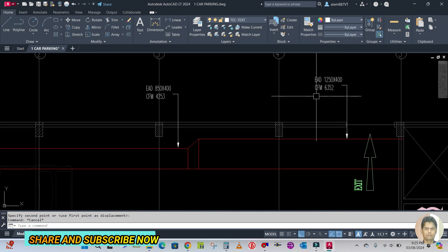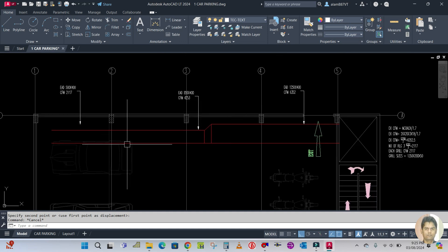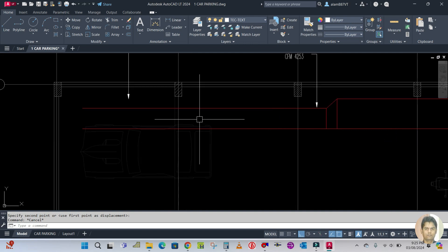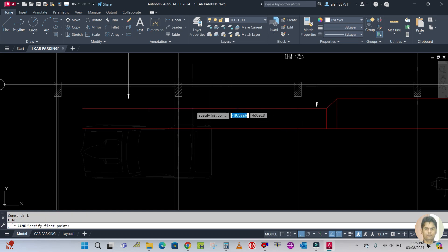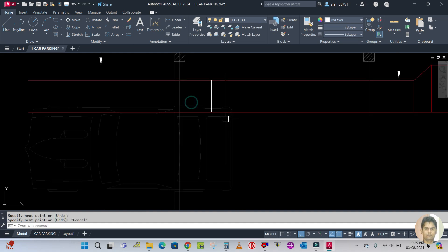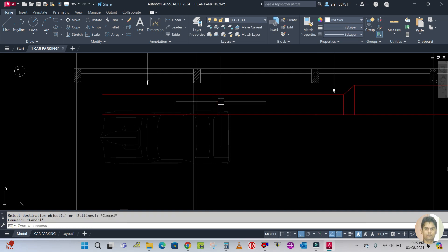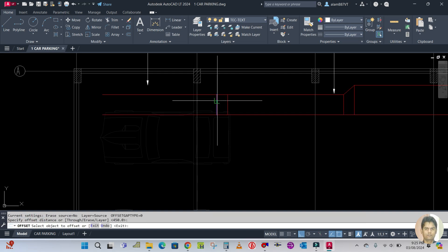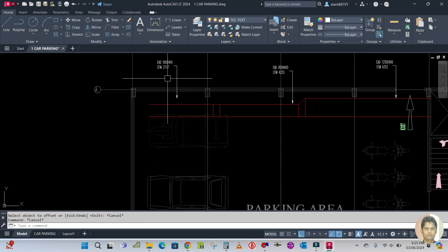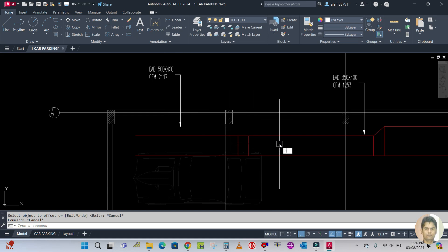The duct size here is 1250 by 400 and here is 850 by 400. One more reducer will be coming here — draw one line here like this. Use MA for match property, match this line, offset 450. The duct size here is 500 by 400, so offset again.